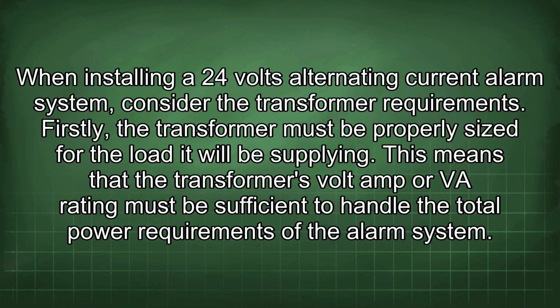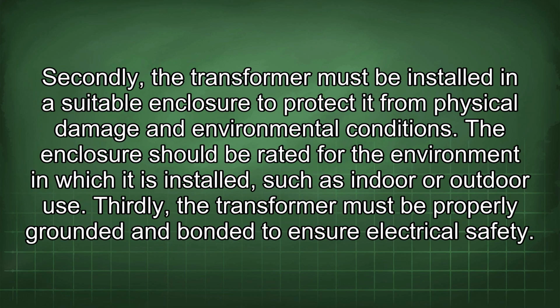When installing a 24 volts alternating current alarm system, consider the transformer requirements. Firstly, the transformer must be properly sized for the load it will be supplying. This means that the transformer's volt-amp or VA rating must be sufficient to handle the total power requirements of the alarm system. Secondly, the transformer must be installed in a suitable enclosure to protect it from physical damage and environmental conditions. The enclosure should be rated for the environment in which it is installed, such as indoor or outdoor use.